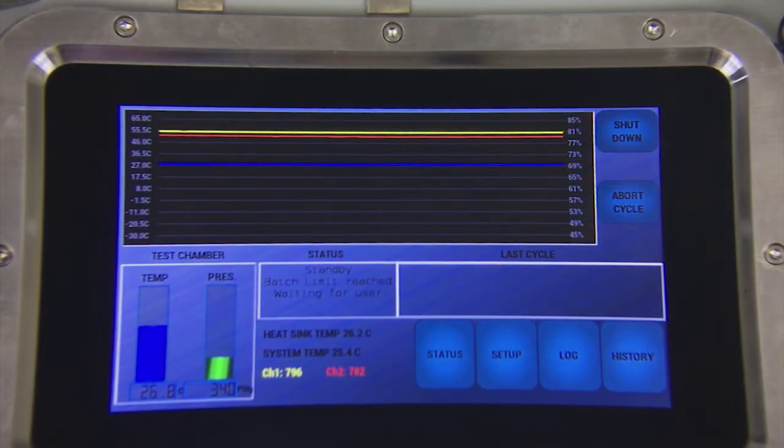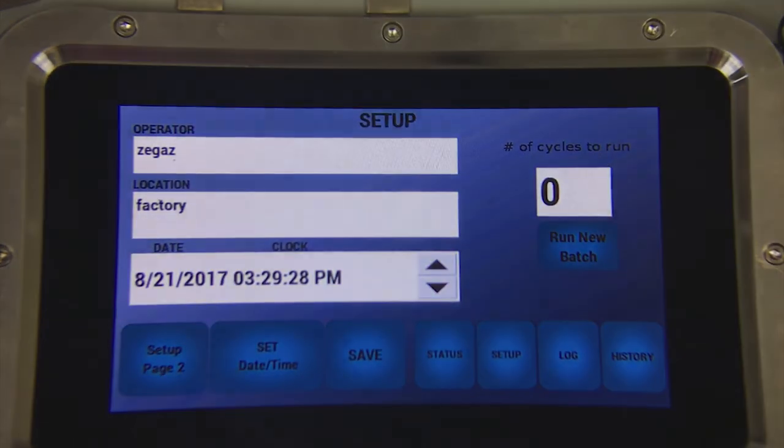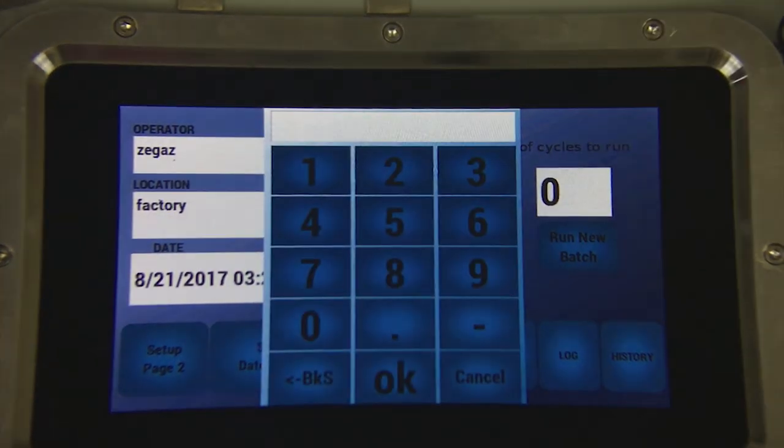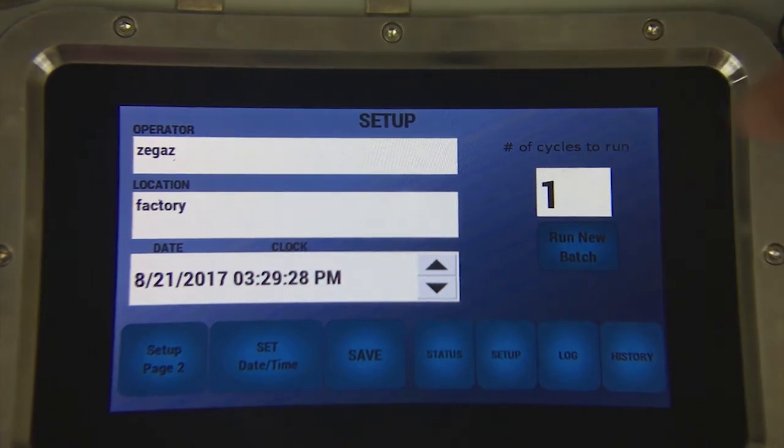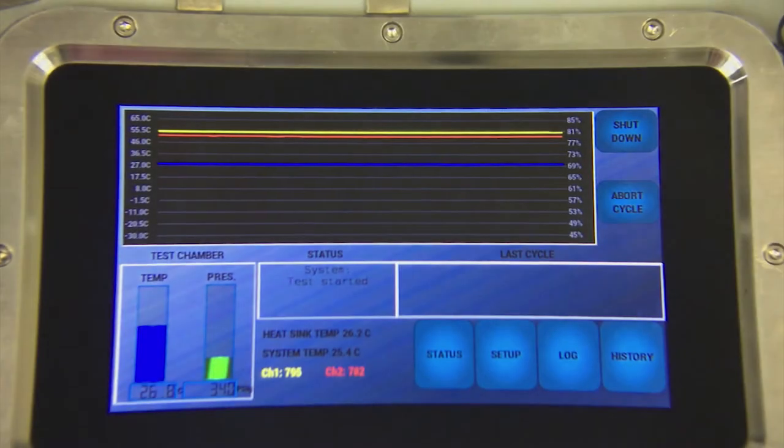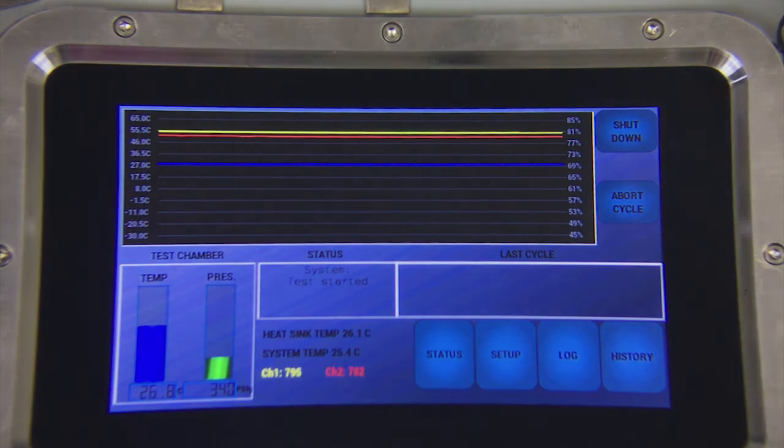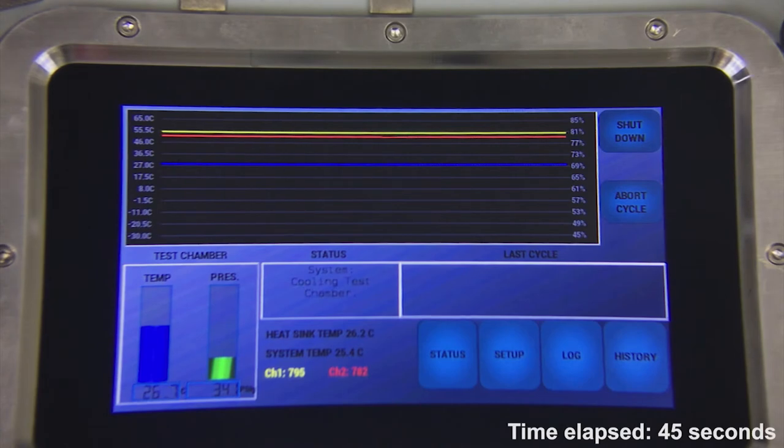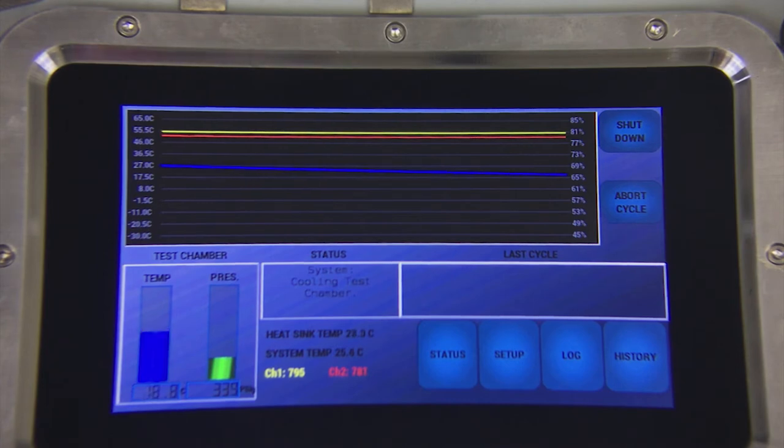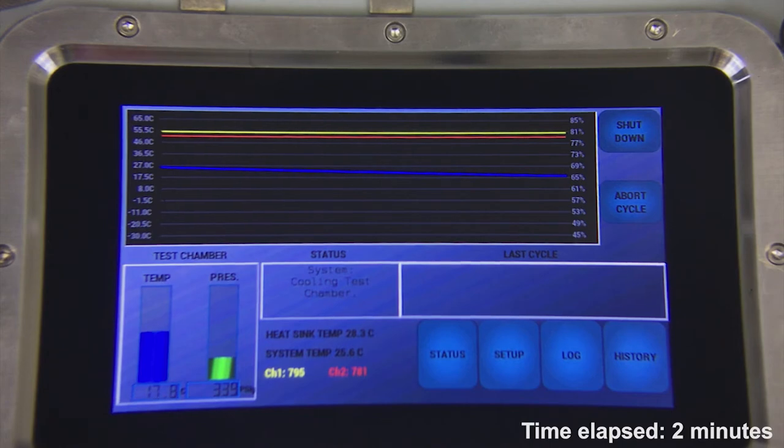Once you are ready to begin running test cycles, return to the setup page and select the number of runs you would like to perform. Push run new batch and return to the status screen. Note that the system status says test started. Once the cooler turns on, the status box will say system cooling test chamber. Notice the blue line on the graph begins to fall with the temperature of the cooler.